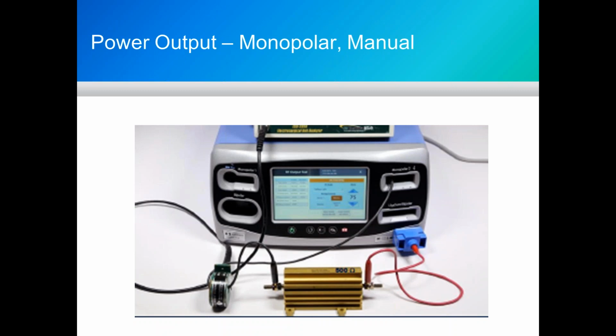And one thing we should comment again as we start to talk about power testing is we always think of this as a pure DC resistance. We're setting 300 ohms, or we're setting 500 ohms, or we're setting 100 ohms, what be it. But really what's important to the generator is the impedance of that value, because we're switching, I think this unit, if I remember correctly, is switching somewhere around 450 kilohertz.